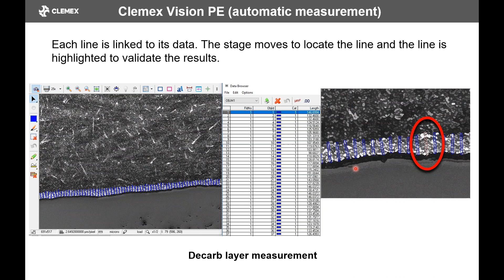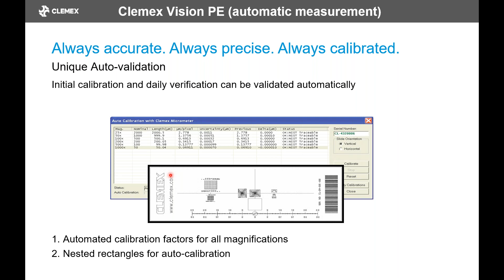Regarding calibration, we have this tool that is very useful, especially if you get audited. This one allows an automatic calibration. Basically, it will detect the serial number. It's not this one here, but the one inside that little rectangle. There's a barcode, and it will detect the serial number and apply the calibration of that serial number to the area that you're measuring, as it was originally defined during the certification. So it's quite useful, and you have a NIST certificate along with it.